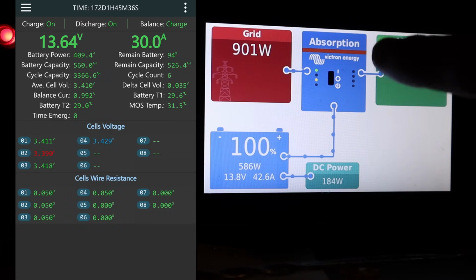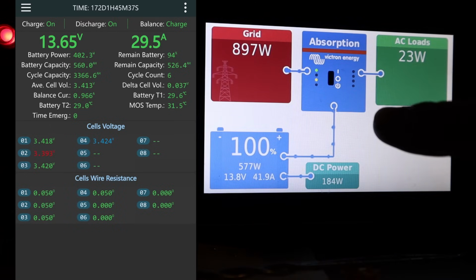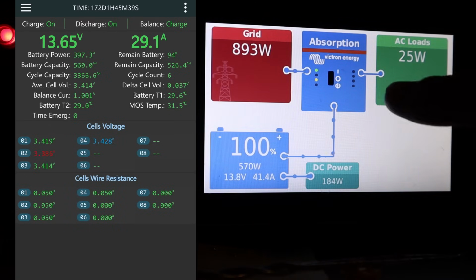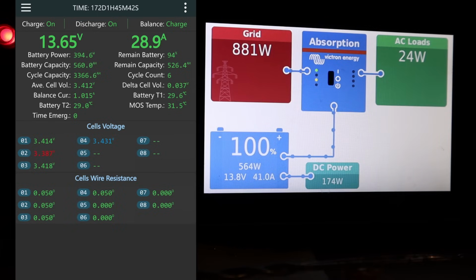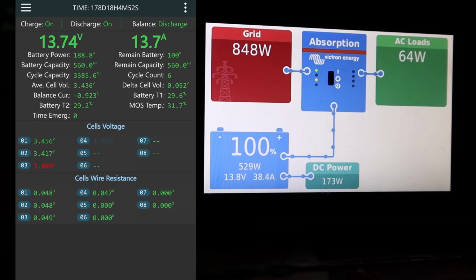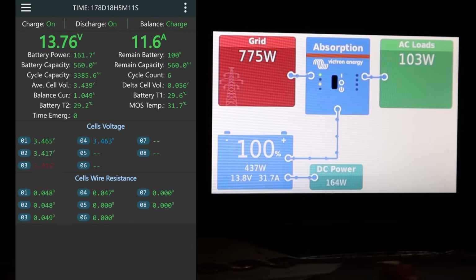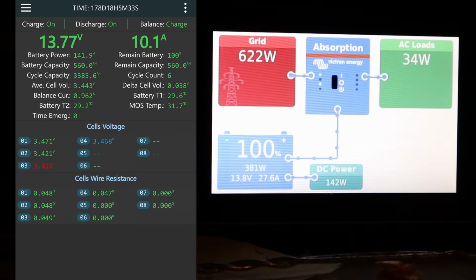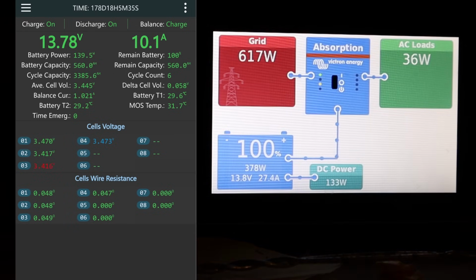What I want to do before I turn on the Phoenix is make sure this is going to hit 13.8 and the BMSs don't disconnect. So 13.7, 13.76. The power from the grid is dropping because this battery is only taking 10 amps now.